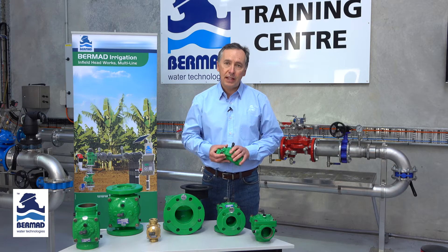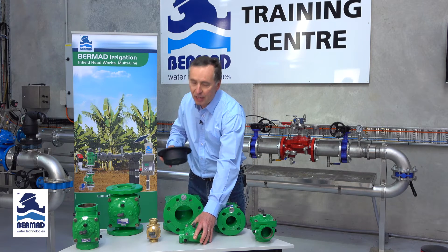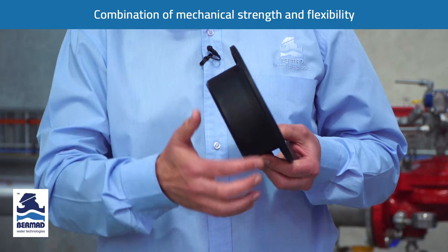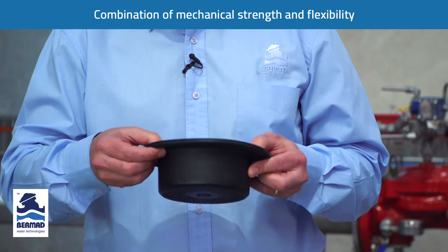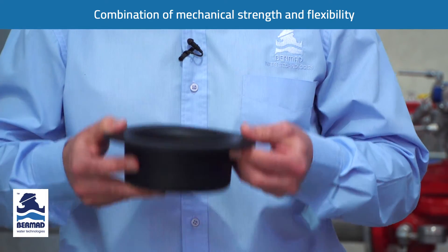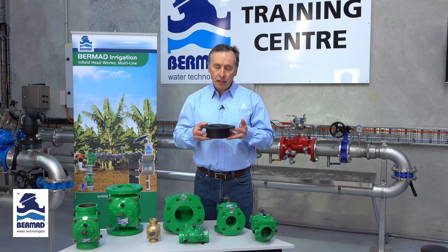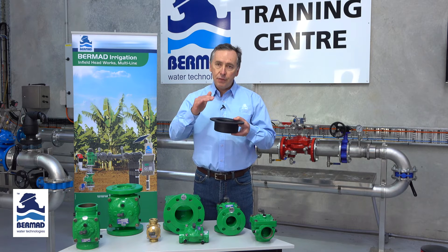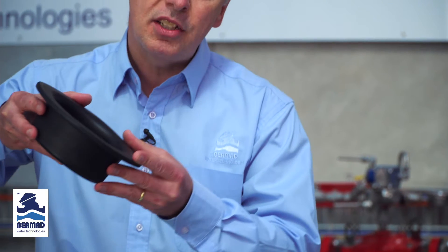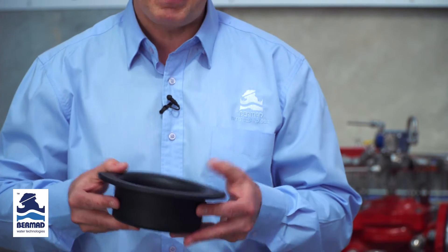The challenge for most manufacturers when using valves in irrigation is that when the diaphragm is the primary product used to control the opening and closing of the valve, you need a combination of both mechanical strength and sensitivity for flexibility in the diaphragm in order for the product to regulate and modulate on and off. Traditional valves like weir type diaphragm valves have suffered over many years through differential pressure conditions, and also in higher velocities where the diaphragm will tend to get dragged to the downstream side.